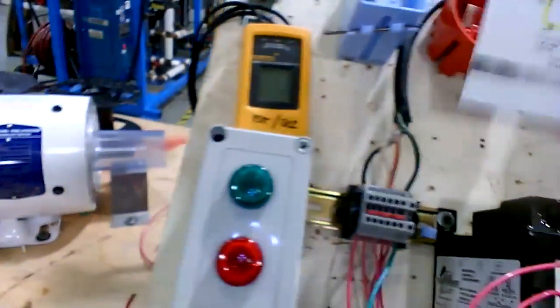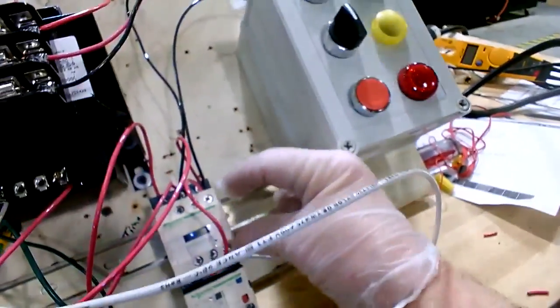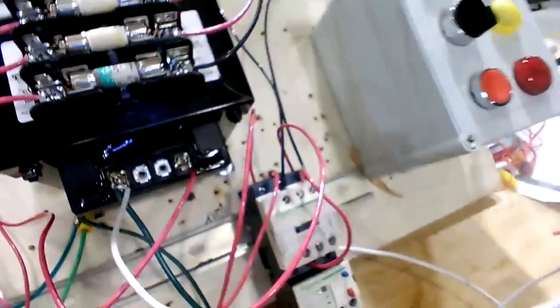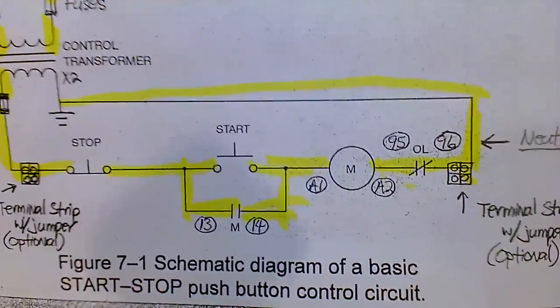Now, the thing that makes the starter pull in is the A1 and A2 terminals that are right here. When you hit the start button, you get power on A1 and A2. So go to A1 and A2 with your meter, and I want you to see that pull in when you hit the start button. So he's going to measure A1 and A2, the coil. That's what actually pulls it in and makes those three contacts close, and the holding contact close on there.